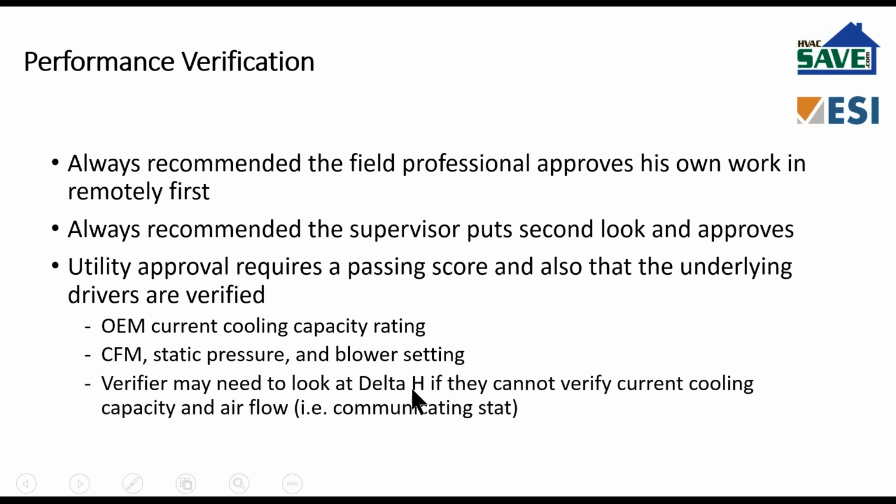So they really don't have to look at this unless they just cannot reconcile some of these other numbers, which obviously can happen if it's a communicating stat and that technician is not submitting CFM based upon what's on the OEM blower charts. It may be that the verifier just wants to give you an idea: hey, are you sure? That doesn't look right.